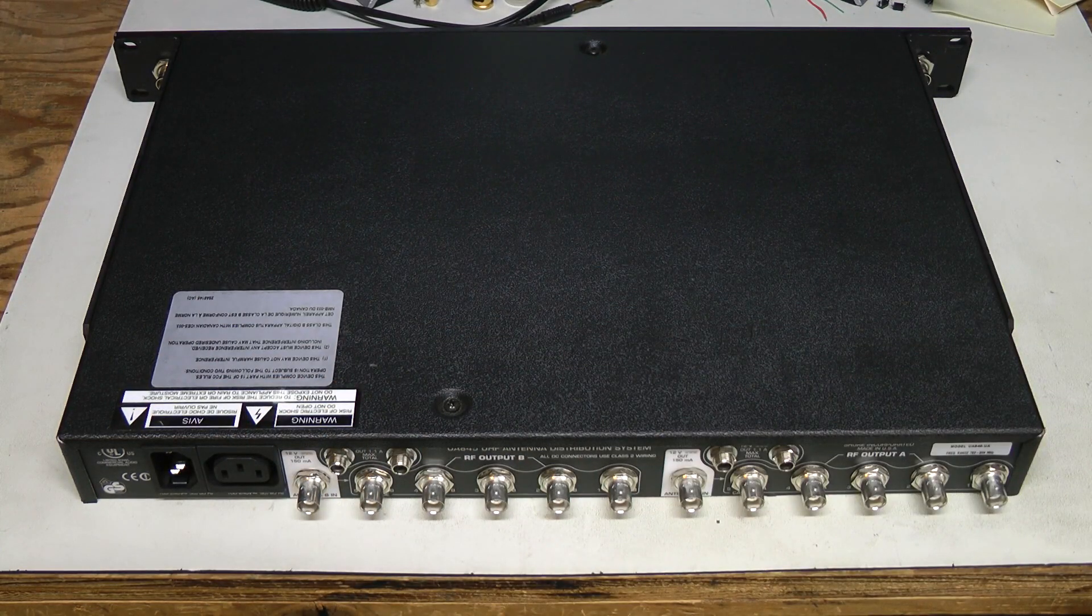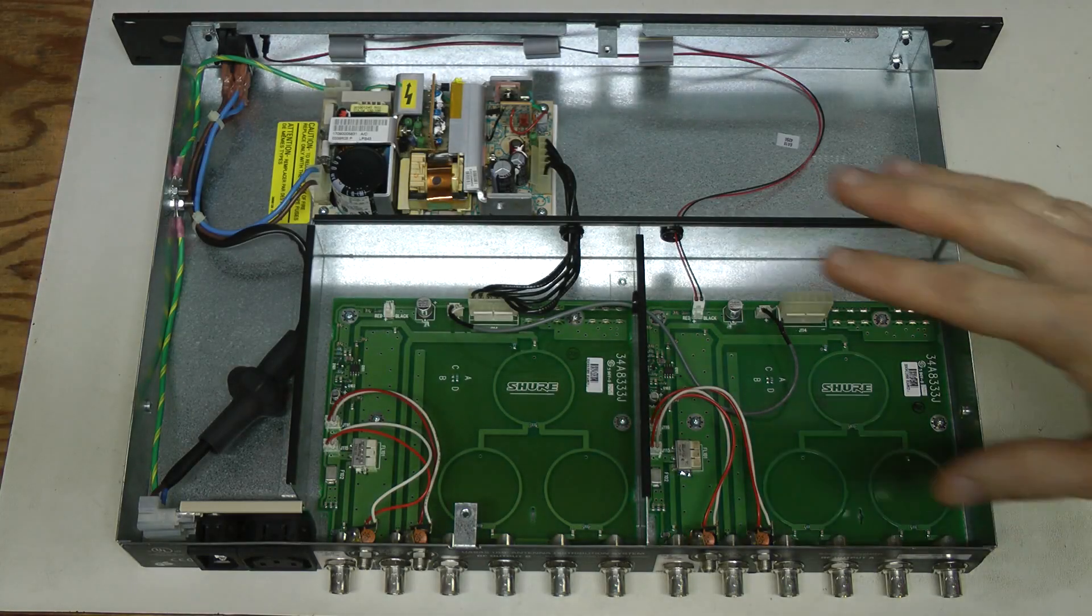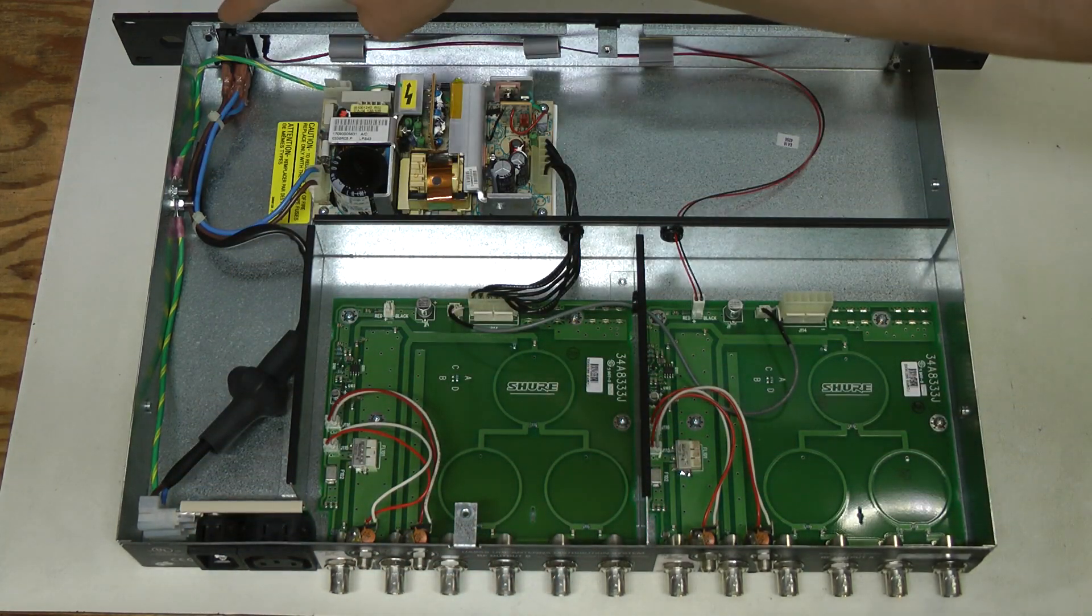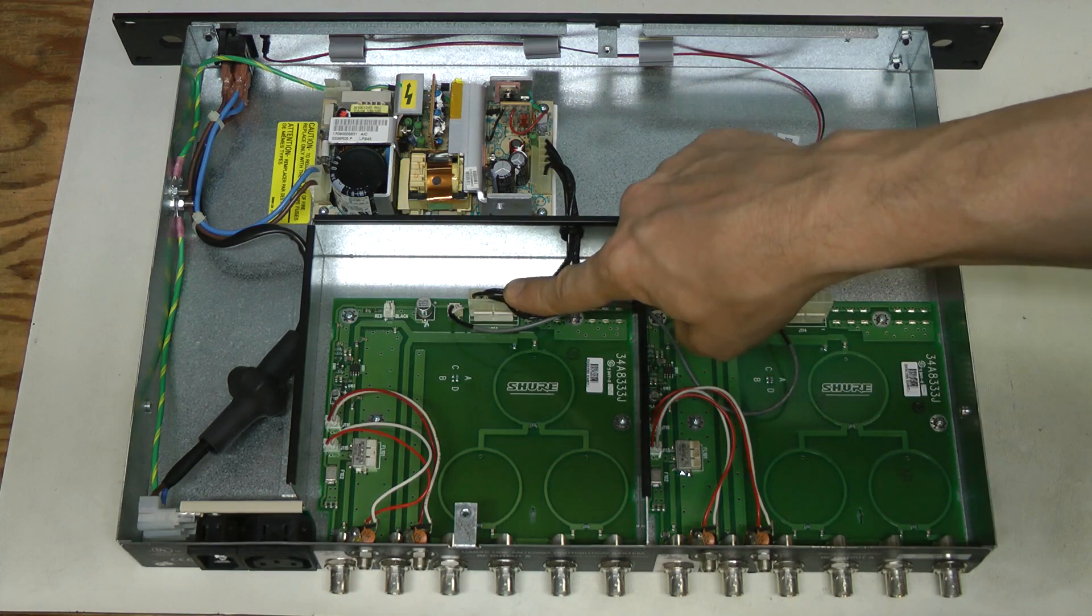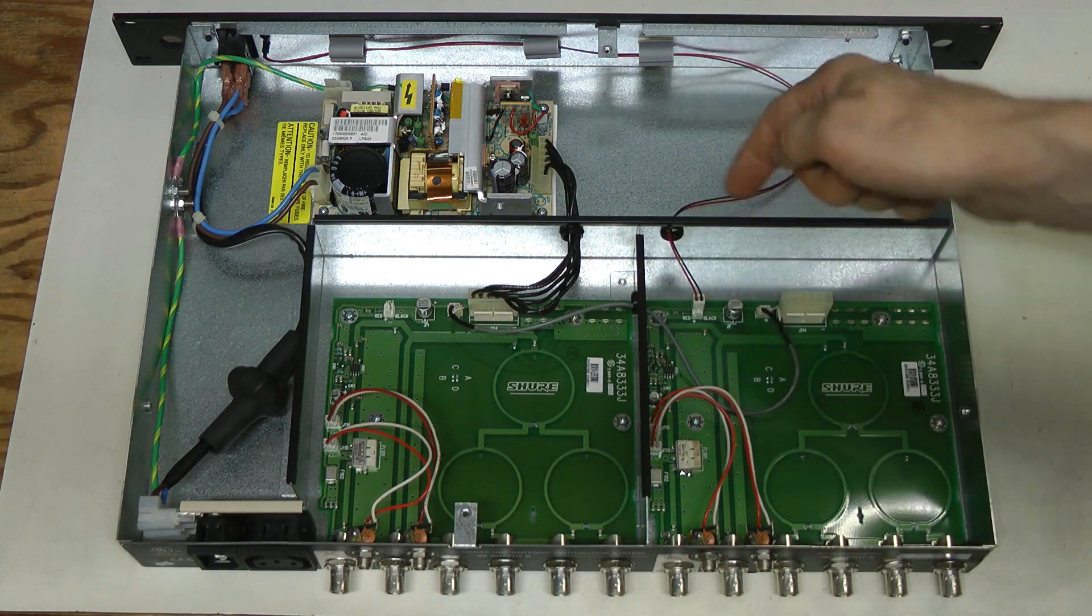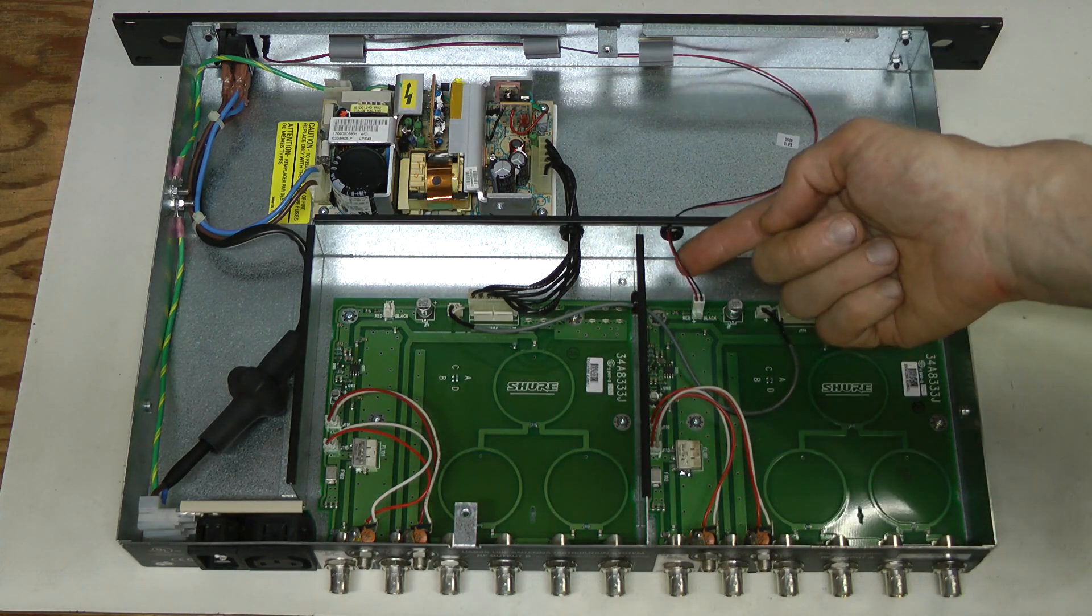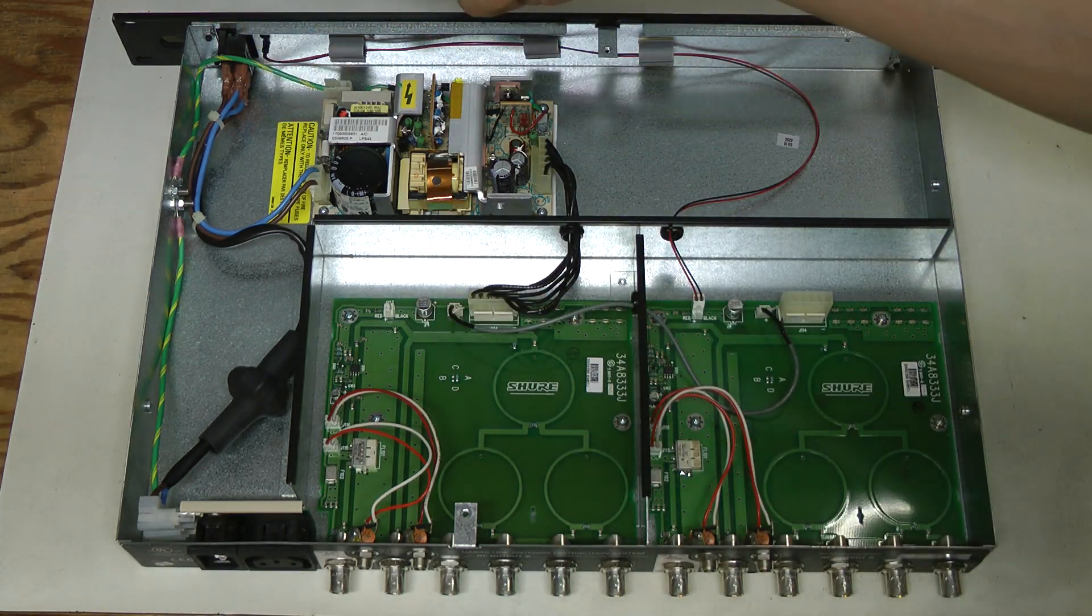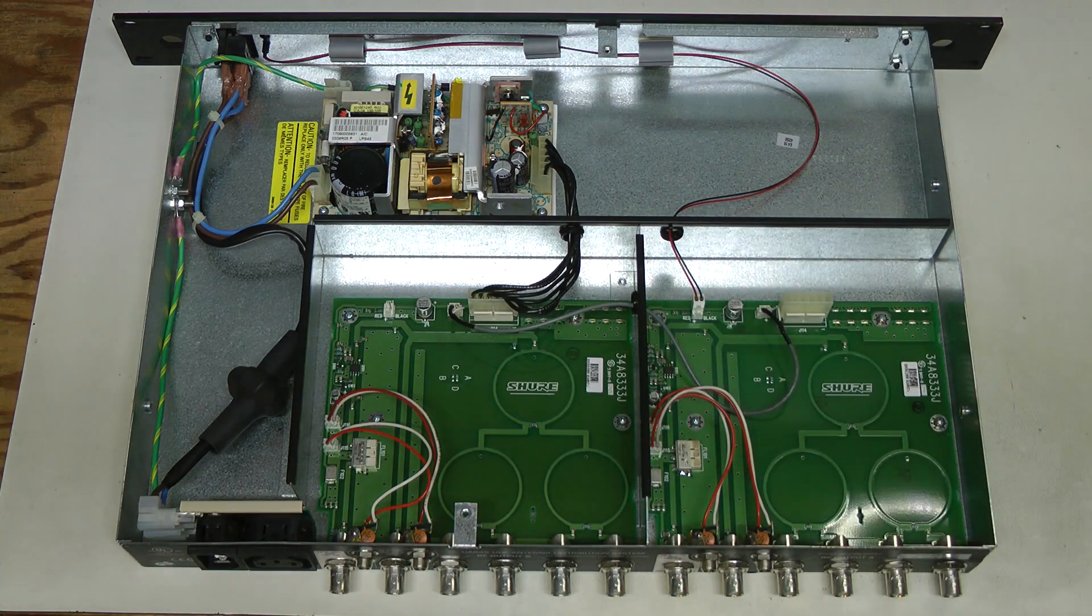So let's take this thing apart and have a look. Try to see what's wrong with it. Here we are. Two identical channels. Mains input is here, then it goes to this power switch, then into the switch mode power supply. The output from the supply is here, goes to this channel, and then there is this jumper wire to the second channel. And from the second channel it goes to the LED. So if LED does not light up that means there is no power here. So let's start checking. First I would check if the fuse is fine here, then if mains power reaches the power supply. And so on. Let's go.